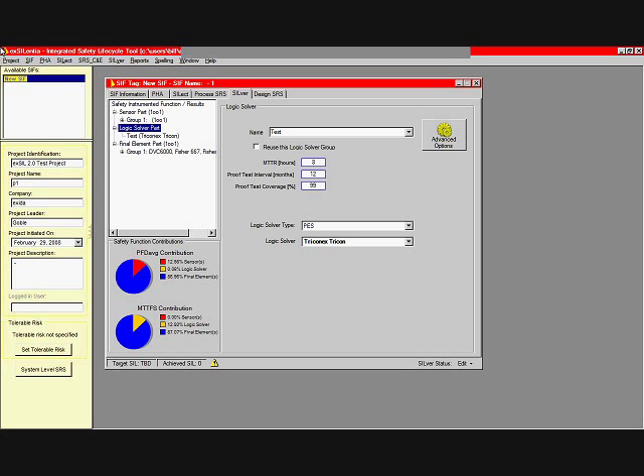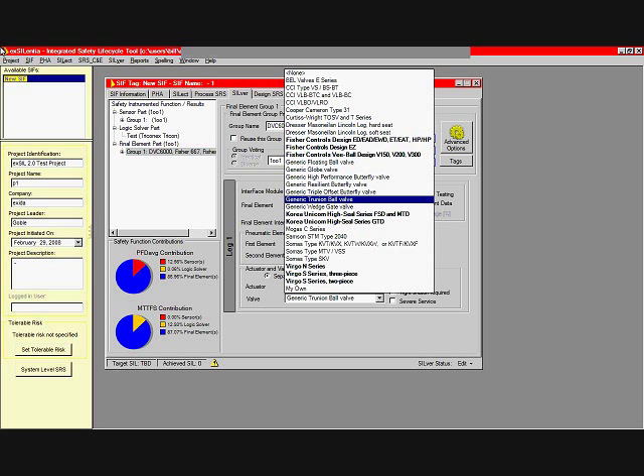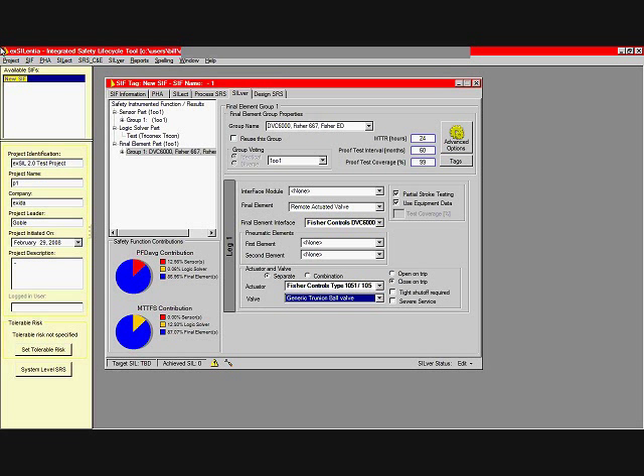So I've got a single Rosemount 3051C. I've got a Triconex Tricon, and I'm going to put in one valve assembly. I'm going to use a Fisher DVC 6000 to interface the Tricon to the actuator. Assume for the moment that we will activate the automatic partial stroke testing. I'm going to use a Fisher 1051 piston type actuator, and I'm not sure what kind of valve to use, so I'll just choose a generic trunnion mount ball valve. Close on trip. I do not need tight shutoff. There is no severe service.